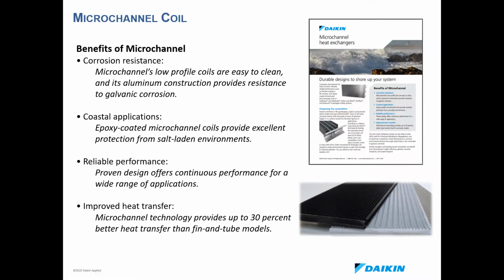All of our air-cooled chillers are going to have the microchannel coils on them. They've got better performance than the tube and fin. They're easier to clean and they're more cost-effective. So that is why these are our choice today. Some of our competitors still offer tube and fin, but these benefits usually outweigh the positives of the tube and fin, like their durability. And then we've got the epoxy coated coil option. Anytime you enter 50 miles or less in DST, it'll automatically put in the epoxy coated coils, and those are done via an E-dip.